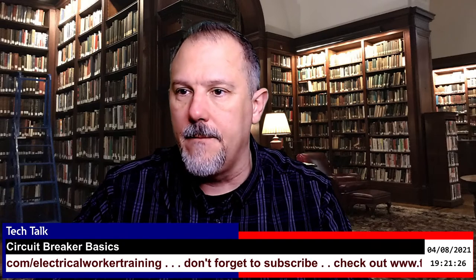James, break down cubicle space. We don't have time for that. I will. Let me just look at some of the questions. Interesting. I'll see if it changes my bus materials. Scott Taylor, excellent, for aluminum to copper when I select 100%. Yeah, check it out, Scott. Check that out. Will it trip at 17 amps? It will not trip at 17 amps. It's still going to be a 20 amp breaker.